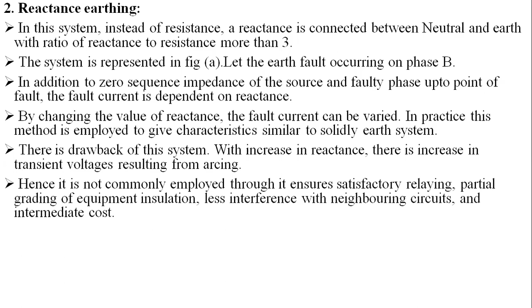So in practice, this method is employed to obtain characteristics similar to a solid earth system. There is a drawback of the system. With an increase in reactance, there is an increase in transient voltages resulting from arcing. Hence, it is not commonly employed, though it ensures satisfactory relaying, partial grading of equipment insulation, less interference with neighboring circuits, and intermediate cost.